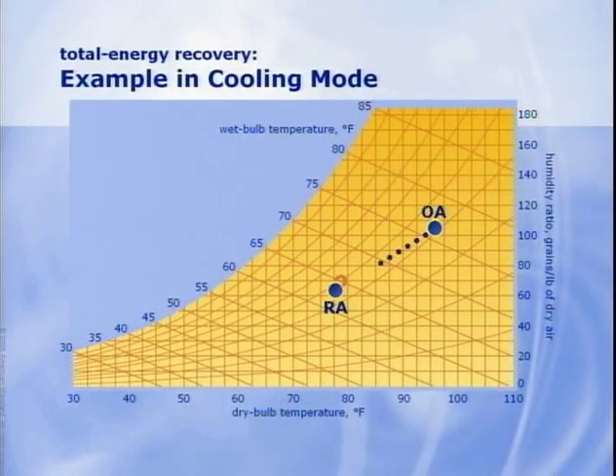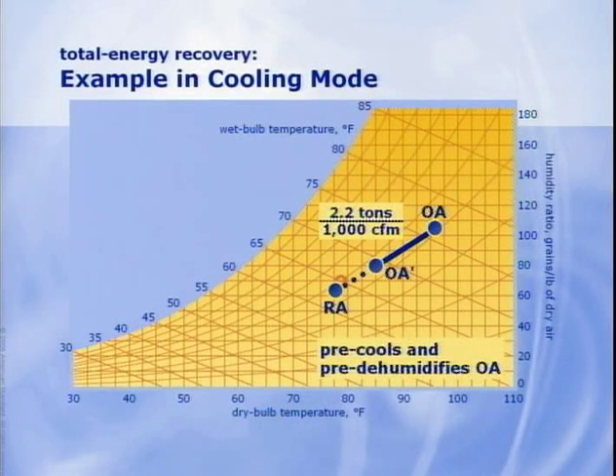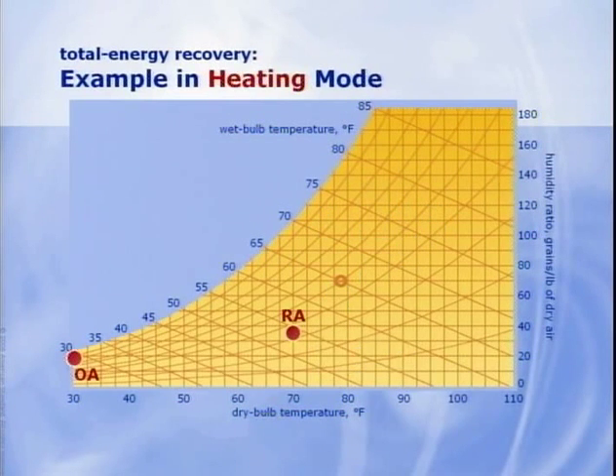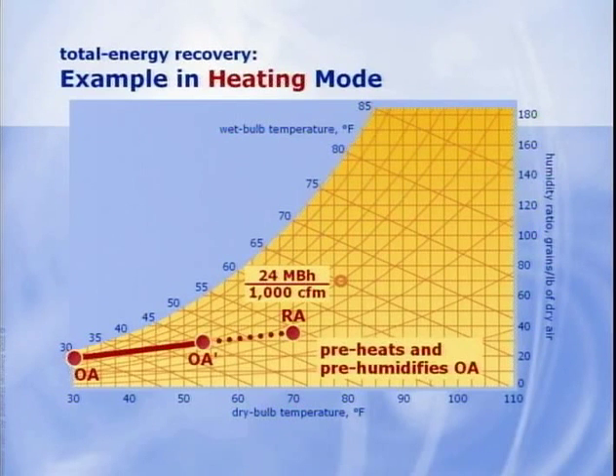The most common technology used in packaged rooftops is probably the total energy wheel. When it's hot and humid outside, the wheel transfers sensible heat and moisture from the outdoor air to the cooler, drier exhaust air stream. This pre-cools and pre-dries the entering outdoor air, saving cooling energy. When it's cold outside, the wheel transfers sensible heat from the warmer exhaust air leaving the building and uses it to preheat the entering outdoor air. This saves heating energy.